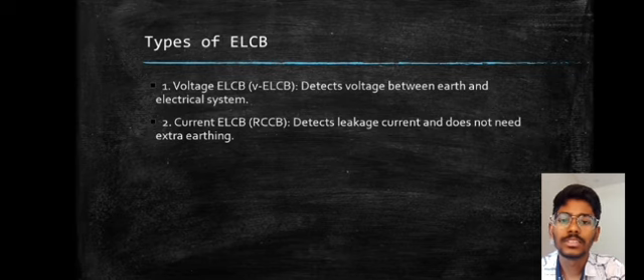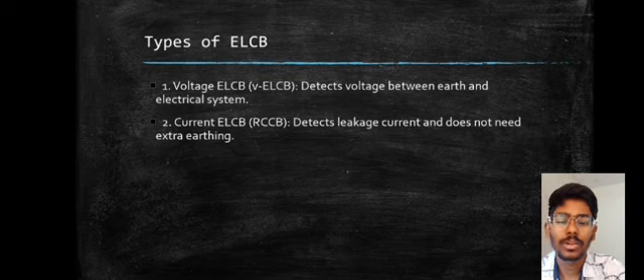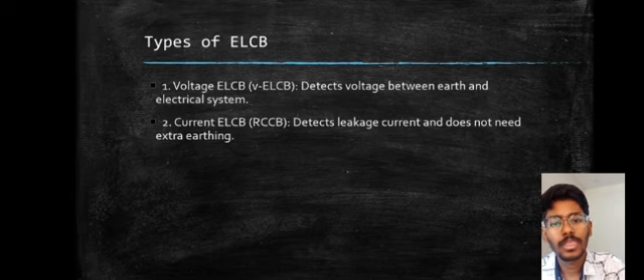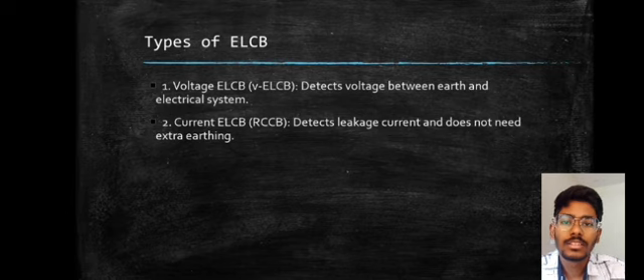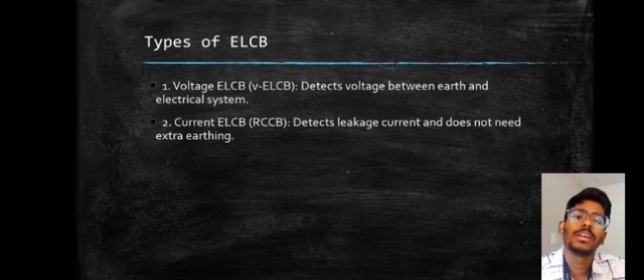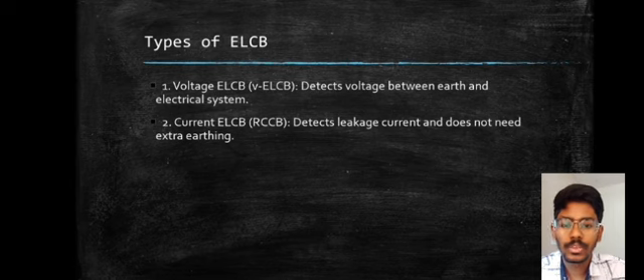There are two types of ELCBs, the voltage ELCB and the current ELCB. The voltage ELCB detects the voltage difference between the earth and the electrical system. This type of ELCB is now outdated and not commonly used. The other type of ELCB is the current ELCB, or you can name it also as RCCB. It is a kind of ELCB which detects the leakage of current in the electrical circuit and does not require any separate earthing connection. This is the most commonly used ELCB today.